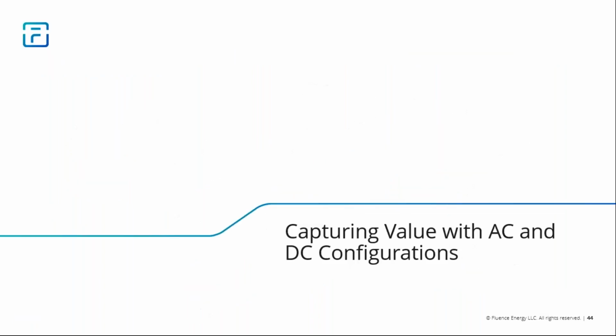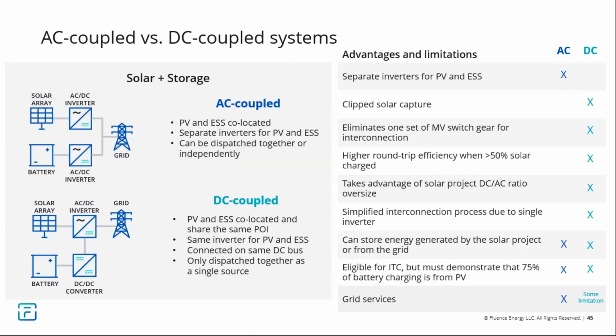The next thing I wanted to touch on is some key decisions around solar plus storage between AC coupling and DC coupling. At a high level, AC coupled systems have independent inverters for the solar asset and storage asset, but are still co-located, often sharing some balance of plant equipment and a single point of interconnection. Whereas in DC coupled systems, the solar and storage assets share a single inverter and are connected on the same DC bus, allowing the storage asset to be charged directly with solar generation.